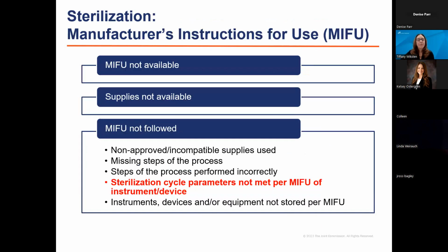So just some common observations. I'm not going to spend too much time going over these, so we have some time at the end for questions. But what I want to point out on this slide is in red, right? This is where immediate threat to health and safety gets evaluated and sometimes determined, right? So if the sterilization cycle parameters are not met per the manufacturer's instructions for use of the instrument or device. So sterilizers will sometimes provide general sterilization cycle time and temperatures. Sometimes your sterilization accessories will provide general sterilization cycle time and temperatures. You can't use those in place of the instrument or device manufacturer's instructions for use.